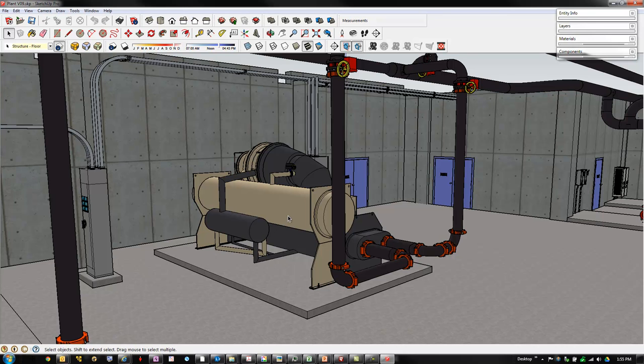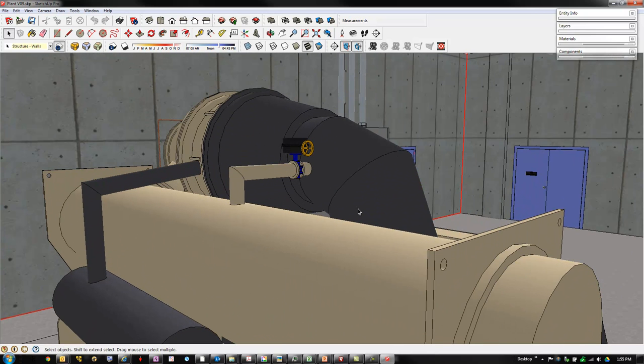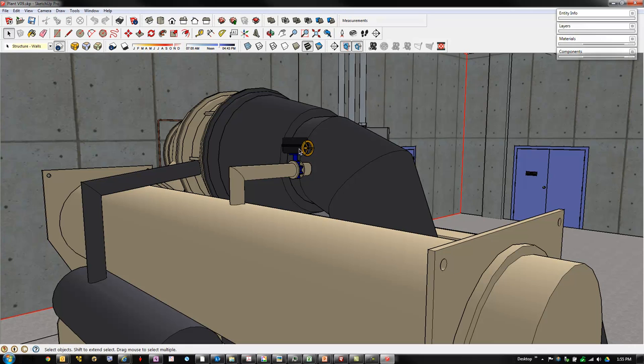So now you sort of understand how this machine works, and in fact how the other machine works, but there are still these differences. In other words, the reason we got into that is, what would this thing be doing? There's this gizmo that has some sort of control valve in it that connects the suction elbow with the condenser. Well, if you've been around refrigeration, you've probably heard people talk about hot gas bypass, and that's exactly what this is. This is a hot gas bypass connection.